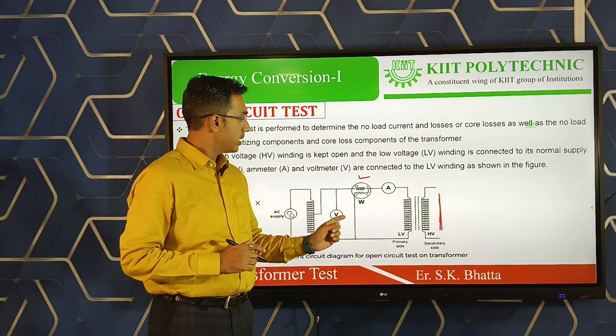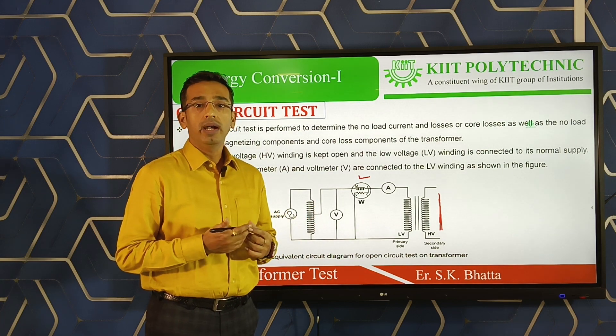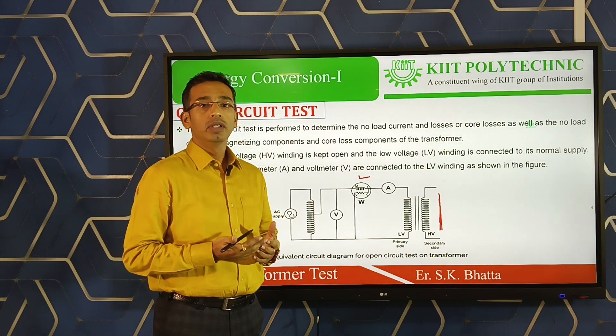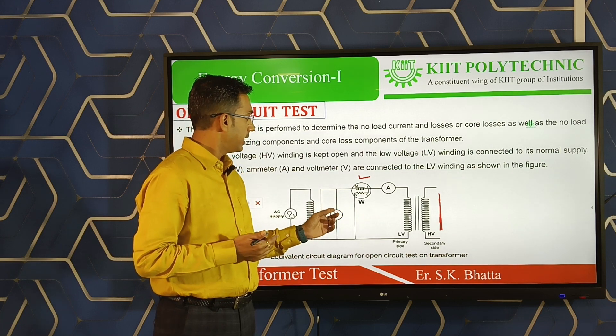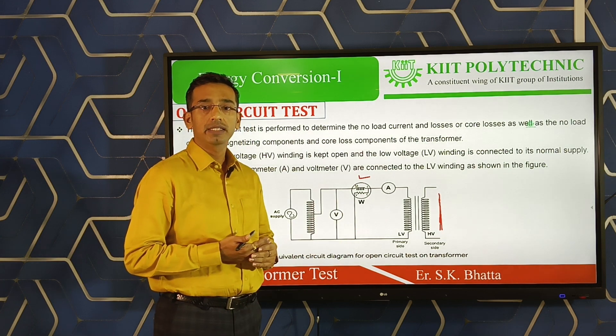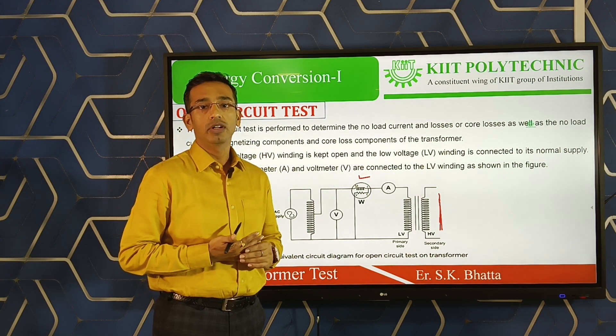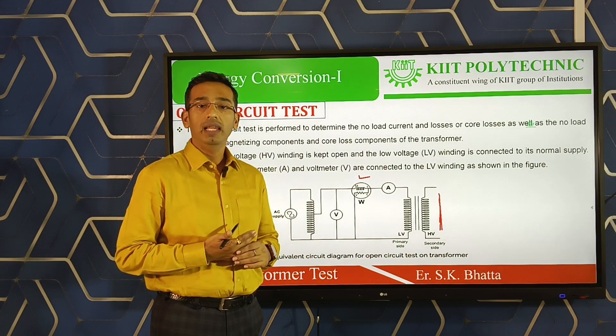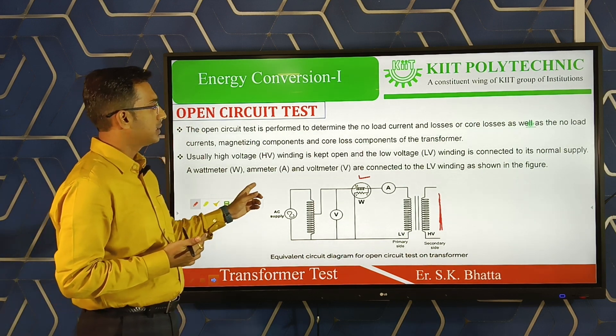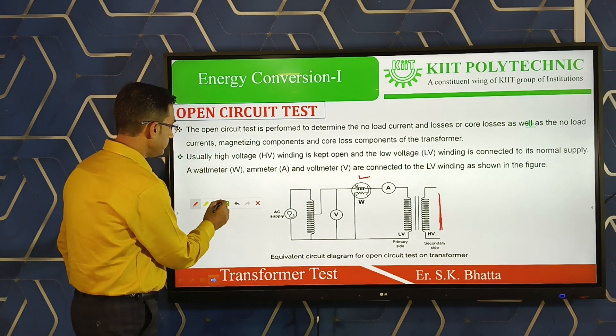The reason we conduct this test on the LV side is because this is the low voltage side, and this test requires rated voltage. In the LV side, the rated voltage is lower and can be safely handled by the instruments — ammeter, voltmeter, and wattmeter. That is the purpose of conducting the open circuit test on the LV side of the transformer.